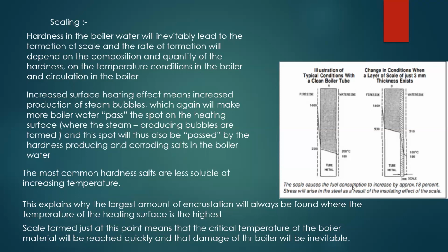So the scale caused the fuel consumption to increase by 18%. So when there is scale, your fuel consumption will increase by 18%. Stress will arise in the steel as a result of the insulating effect, because your scale gives an insulating effect.